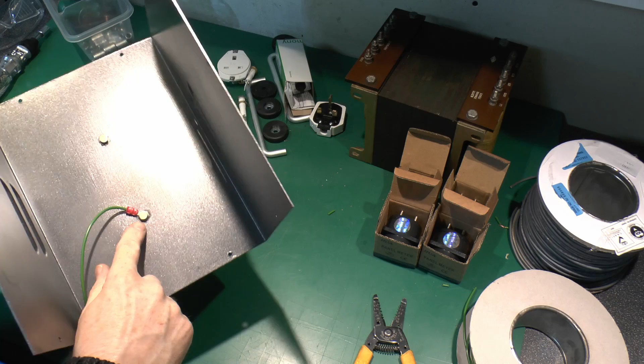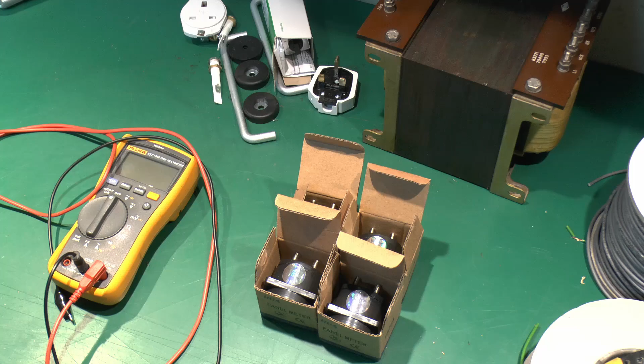On the inside, I've fitted a lead for the earth connection, and put that under one of the bolts to clean off a bit of the paint underneath, then crimped on a lug and secured that down. This will act as the earth connection both for the handle and the whole top of the case, because we don't want to rely on the little holes where it screws into the bottom one, since it's all basically painted on all sides. So that's the top part completed.